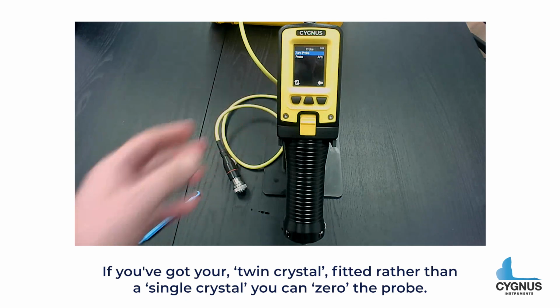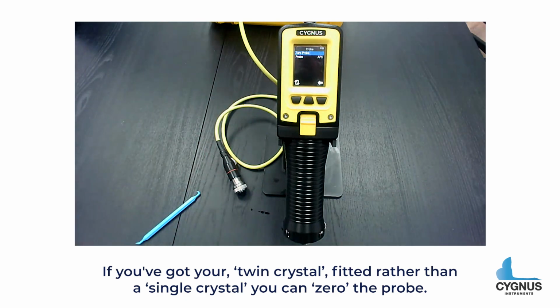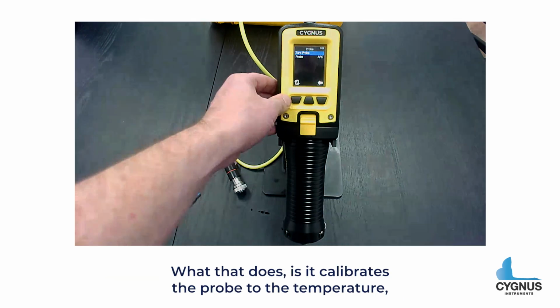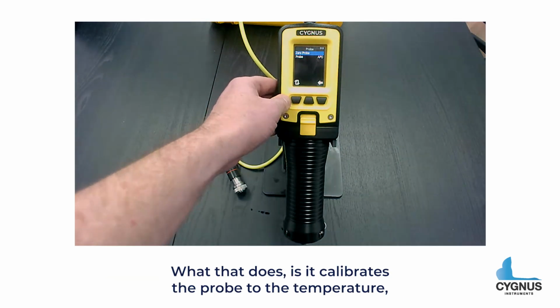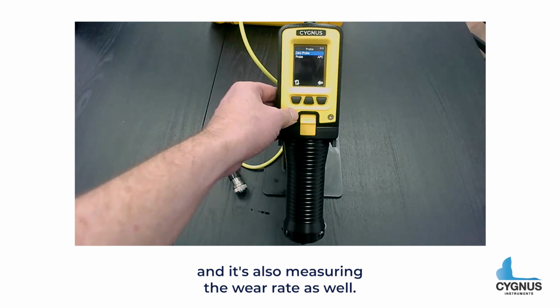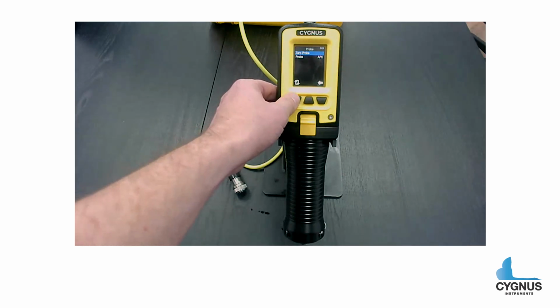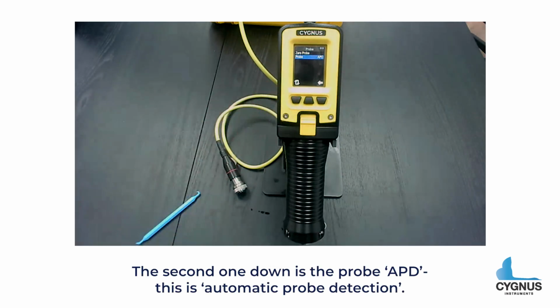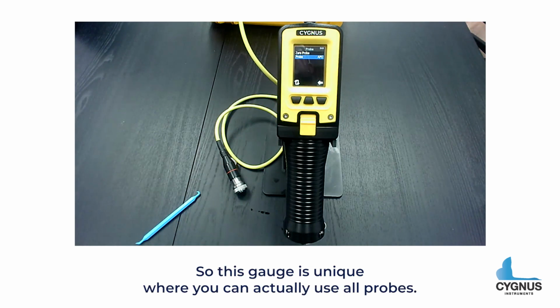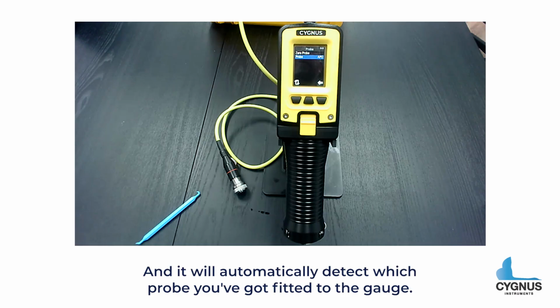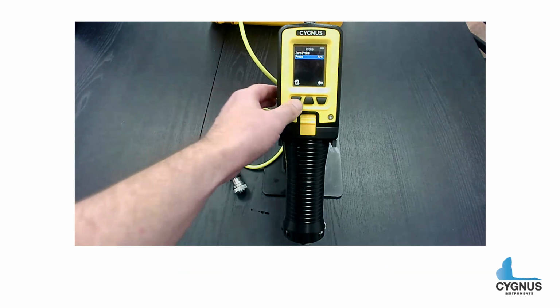If you've got your twin crystal fitted rather than a single crystal, you can zero the probe. What that does is it calibrates the probe to the temperature, and it's also measuring the wear rate as well. The second one down is the probe APD. This is automatic probe detection. So this gauge is unique, where you can actually use all probes and it will automatically detect which probe you've got fitted to the gauge.